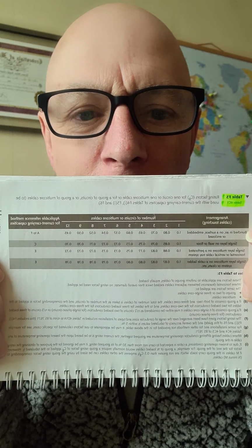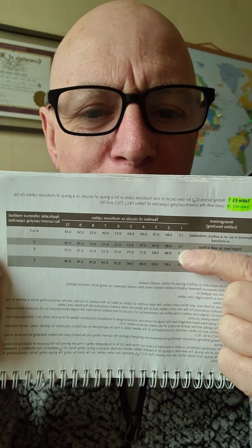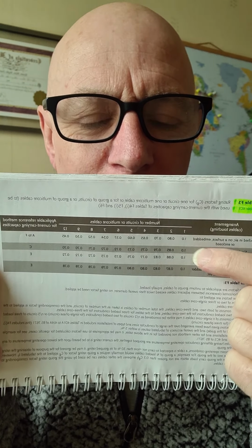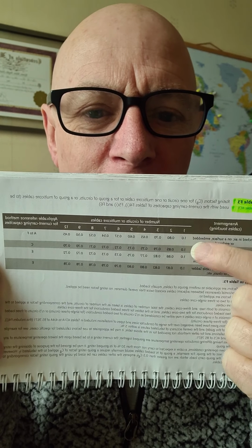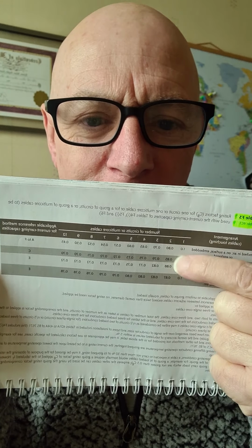Finally, for the calculation for IT, we've got our grouping factor, and grouping factor here is table F3, and it's looking at cables that are bunched together. And then you've got the number of circuits. One thing that's really important to remember here is that you're taking into account other circuits plus the circuit that you're installing. So don't make the mistake of thinking that if there's one other circuit, you're only looking at one. You'd be needing to look at two to take into account both of those circuits.